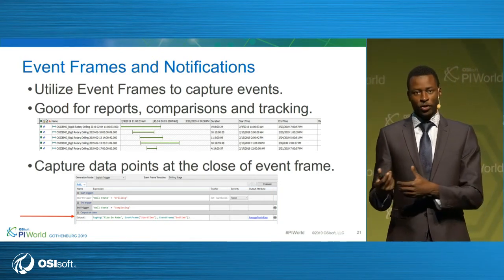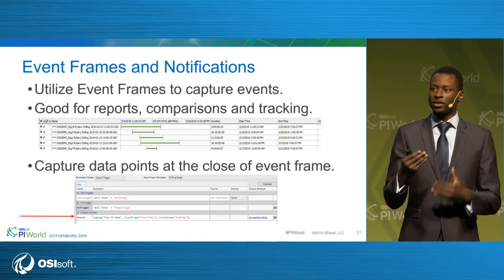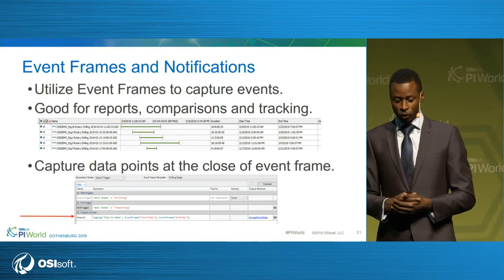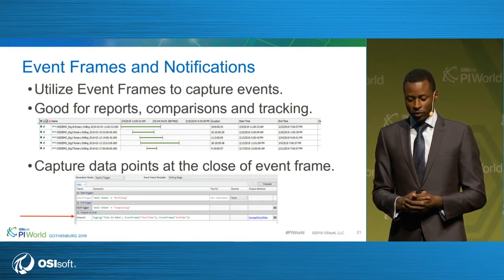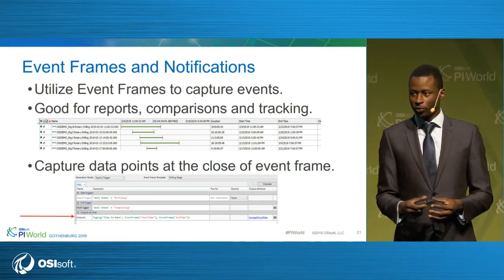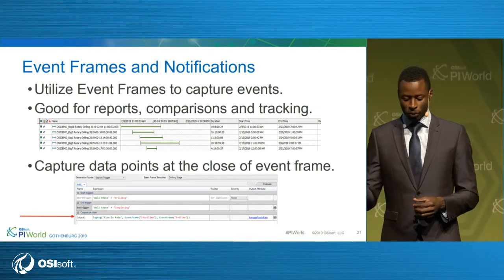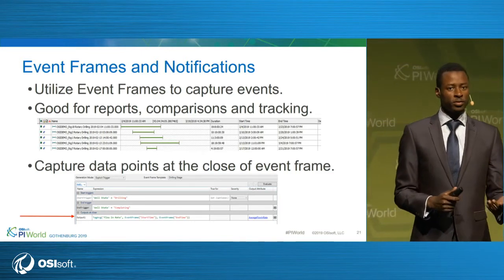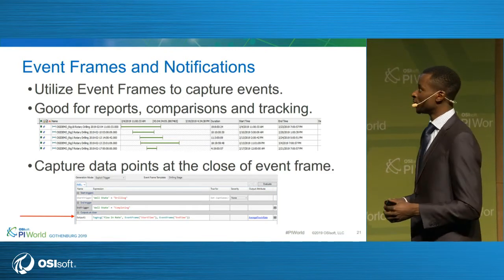So these event frames can then be used in reports or to allow you to do comparisons against these different event frames and also do some form of tracking as well. It also allows you to capture data points at the close of the event frame, so you can see how data points have been behaving. For example, if you look at the image at the bottom there, we have a trigger to start the event frame, and we also have an end trigger to end the event frame.